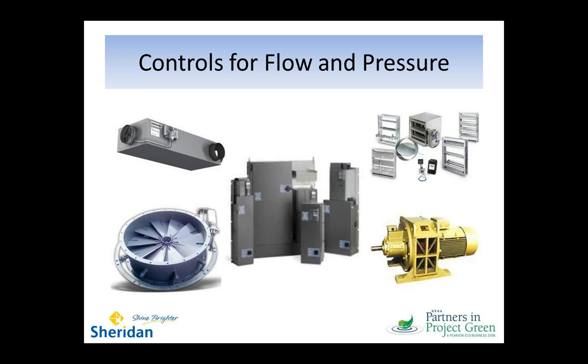Not all controls are created equal, and there are a number of ways that I can control what's going on with my process. I'm trying to match the motor and the load, remember, and keep at that optimum efficiency point. So historically, some of the ways have been dampers and vanes. And you can see at the bottom left, there's an inlet vane damper. So this is closing the vanes to restrict, say, airflow.